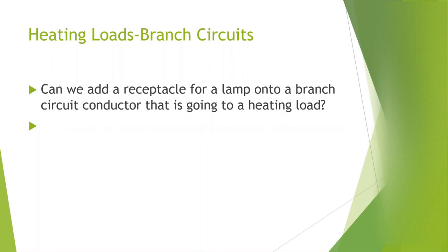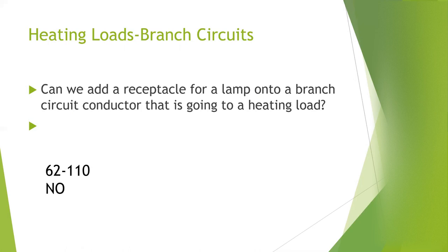Can we add a receptacle for a lamp onto a branch circuit conductor going to a heating load? Where do we find information on heating loads? Section 62 — specifically Rule 62-110. It instructs on branch circuits and states in sub-rule 1 that branch circuit conductors used for the supply of energy to heating device sets shall be used solely for such heating device sets. So the answer is no — a heating load branch circuit is just for the heating load.